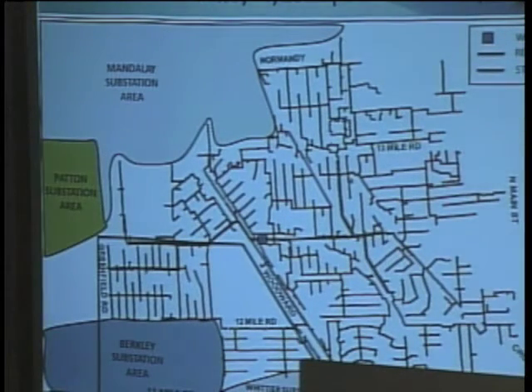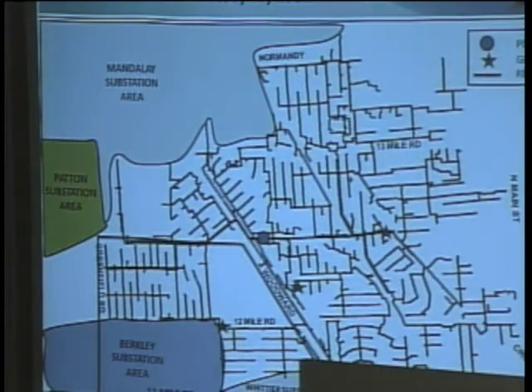So the areas in black were restored the next day, and they could jump over to the Whittier substation, and there's another Mandalay substation, and also I believe Lincoln. These are substations that are around Webster, and therefore we can transfer some of the load and not overload that equipment. The areas in red then had to wait until the next day, in which they started to put in the portable substation and also three generator locations. Those locations were shown where the stars are. One was located near the Civic Center here, and a couple over in the Royal Oak area.